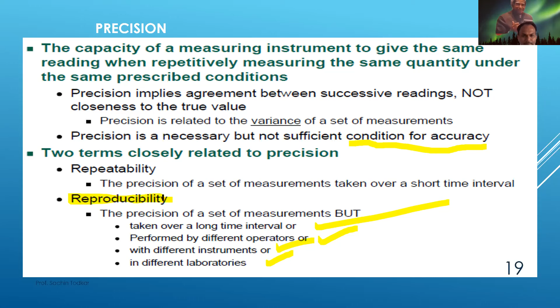Two terms closely related to precision. One is repeatability: precision is taken when there is repeatability in the particular reading. The other is reproducibility, that is, the same reading is reproduced at a very long interval of time, performed by different operators, with different instruments, or within different laboratories. So if there is a change in time, operator, instrument and laboratory, and the same reading still comes, then it is called a reproducible reading. Getting?